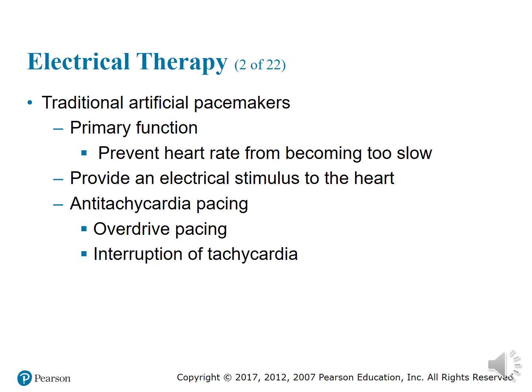Another use for a pacemaker is anti-tachycardia pacing, also called overdrive pacing. This special programming function on some pacemakers allows the pacemaker to interrupt a tachycardia by interjecting a series of paced beats in the middle of a tachycardia, thus interrupting the rapid circuit and allowing the sinus node to resume control.